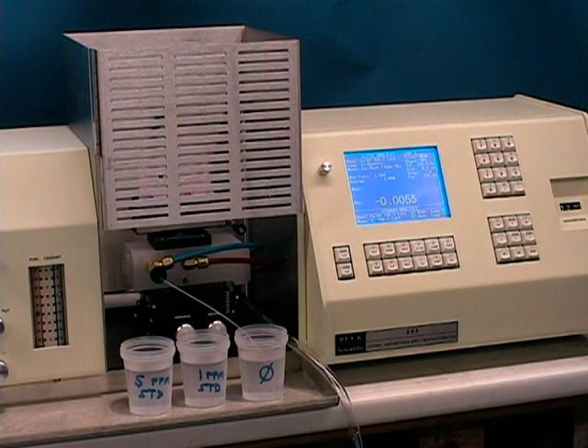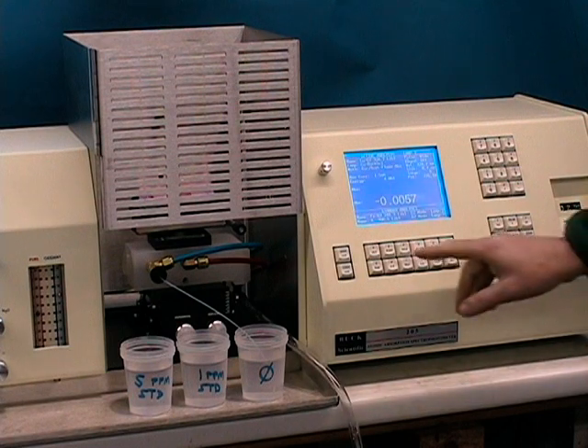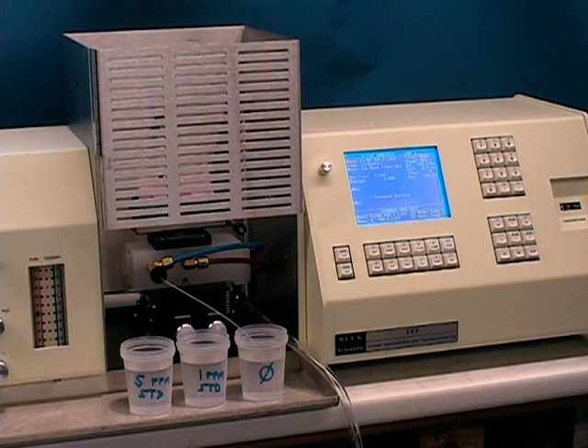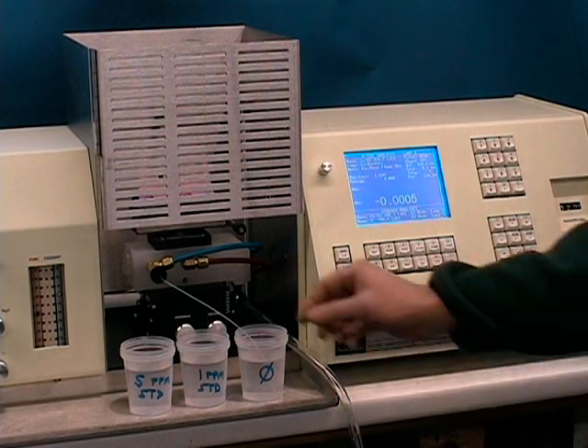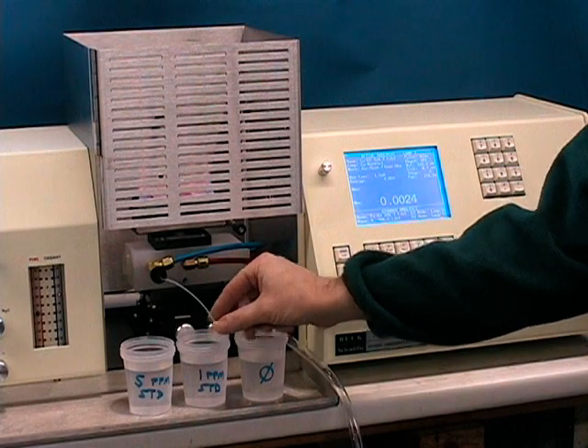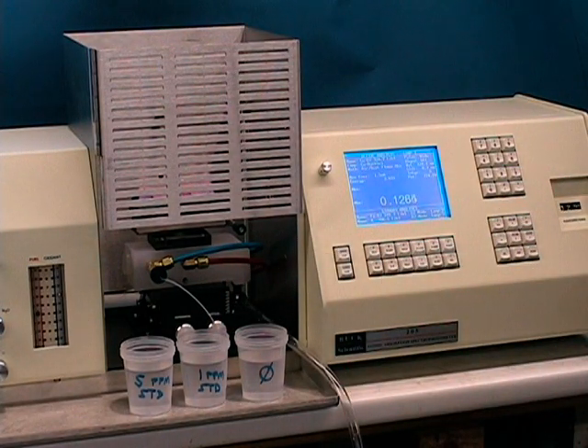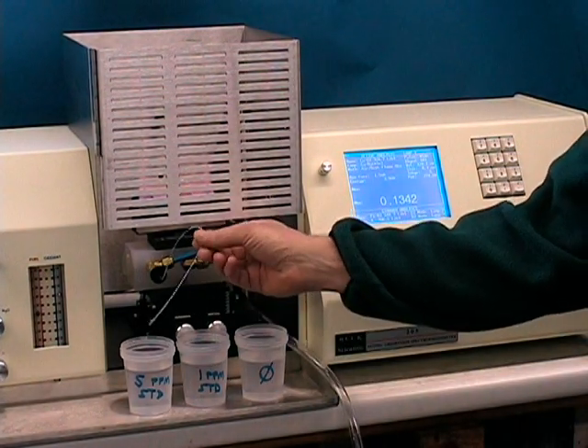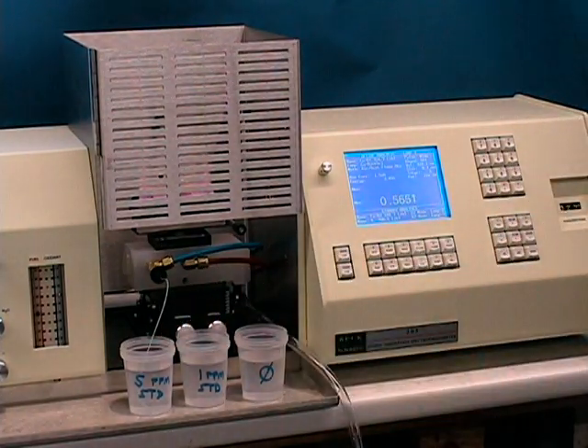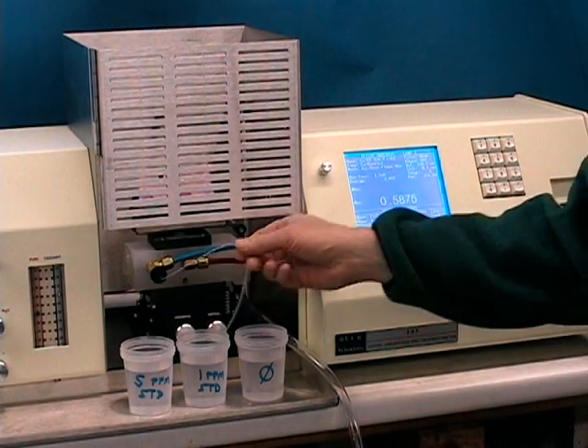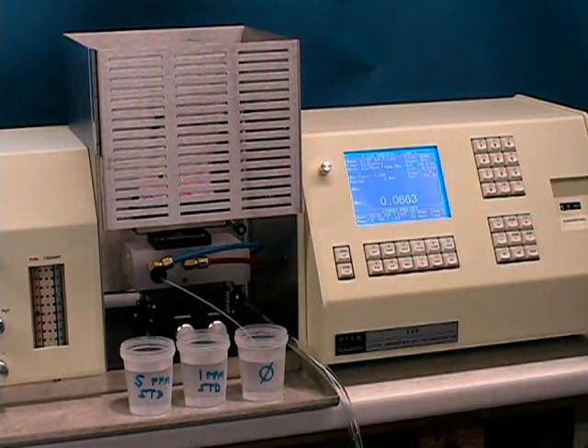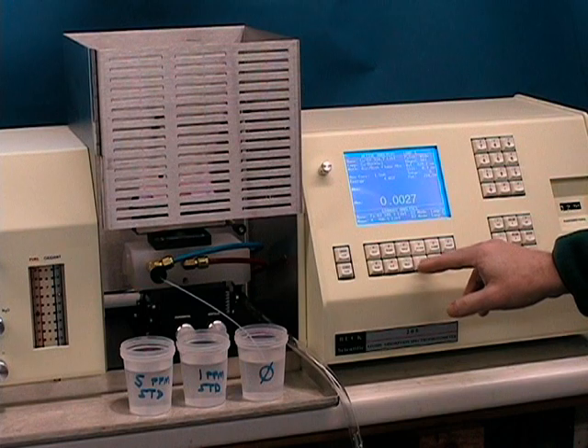Once you have your standards prepared, it is a good idea to press auto zero while aspirating your blank, and then check the absorbance signal, the raw data signal from your standards, just to see that they were prepared correctly. Again, you should see at least a 0.04 absorbance signal for any calibration standard to ensure good stability. Here for copper, we see we've got about a 0.15 for 1 ppm and a 0.6 for 5 ppm. So our standards are in the right approximate range. Go back into your blank. Always wait a few seconds for the solution to equilibrate in the flame, and then we proceed to do our calibration by pressing the Cal key.